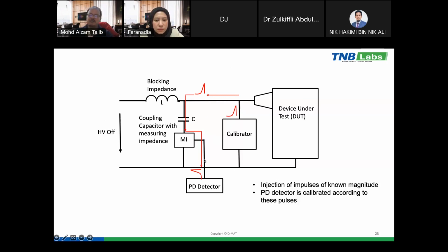So when we apply the higher voltage, a small discharge will occur, and it will be picked up by the coupling capacitor and the PD detector. Because the discharge is very small, normally we use a multiplier based on the previous injection of the signal from the calibrator.